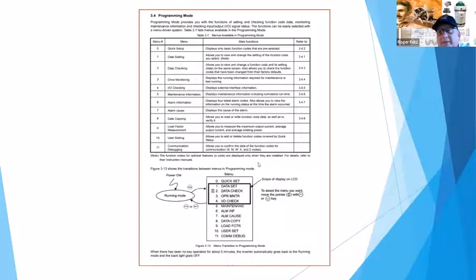This is a little bit more about the menu section of it. Again, the simplicity. I like to find that almost every drive has what they call a quick start menu. That is normally set up, if it's an original piece of equipment, with a set of macros in it that pretty much just open up the parameters that you need to deal with for that given piece of equipment. Because they're used on so many different pieces of equipment, from servos to very simple technology to encoder feedback and reverse direct torque, constant reversing.